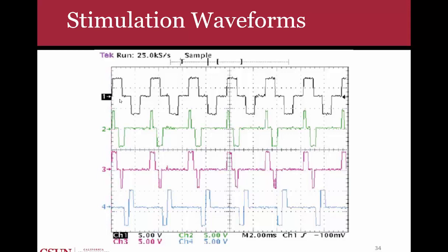You not only have to consider the threshold voltages to actually stimulate the tissue, which goes back to the rheobase and the strength-duration curve for these tissues, but also how much energy, current and charge you're imparting into the tissue. So you should have a better idea of why these waveforms are the way they are, in a very general sense.